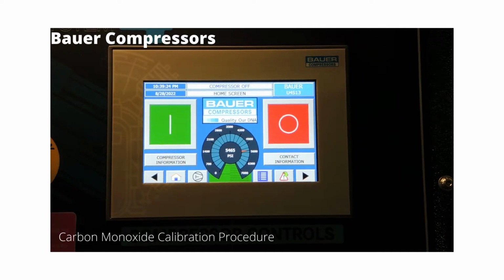This video is going to go over the calibration procedure for the carbon monoxide system on the new Bauer units. This covers several different units, but as long as your screen looks like this and you have the CO monitor as an option, this will be the procedure for it. A couple of things: you're going to want to make sure you have your test gases. It requires 2 test gases.